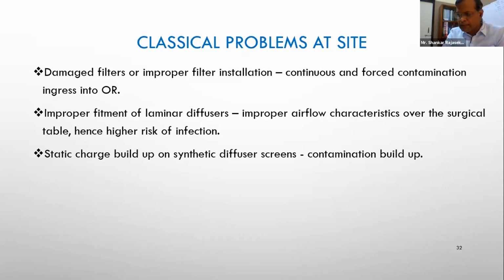And the worst part is, because it is directly above the patient, if it brings in some contamination, it is going to dump it directly onto the patient. Whereas in a turbulent system, the diffuser was not right above the patient, so by the time the contaminant comes into contact with the patient, it would have been diluted. That's why a unidirectional airflow system, when not done properly, increases infection rates in some hospitals.